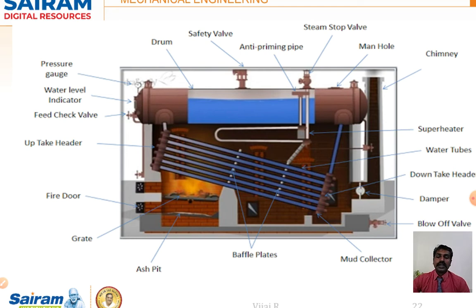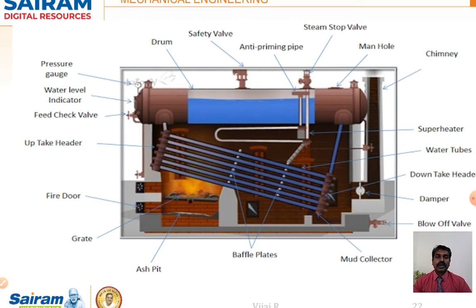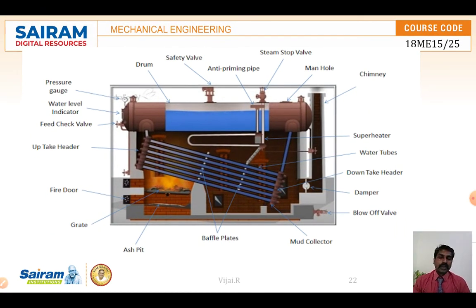The water inside the tubes gets heated up, steam is generated, and the hot steam automatically moves upward through the uptake header, settling at the top of the boiler drum. At the top of the drum there are safety valves, a steam stop valve, and a manhole. A pressure gauge and water level indicator are also present, and the steam is transferred to the turbine through a pipe, causing it to rotate.